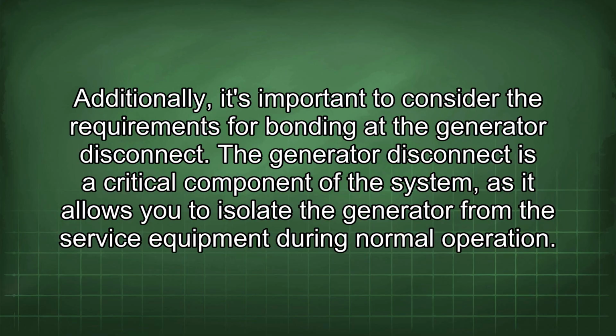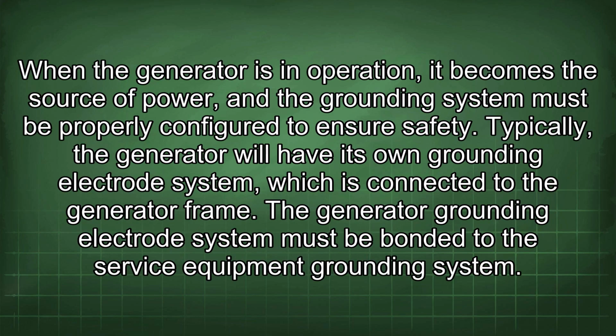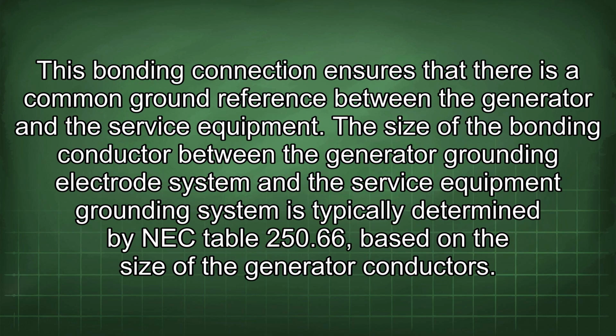The generator disconnect is a critical component of the system, as it allows you to isolate the generator from the service equipment during normal operation. When the generator is in operation, it becomes the source of power, and the grounding system must be properly configured to ensure safety. Typically, the generator will have its own grounding electrode system, which is connected to the generator frame. The generator grounding electrode system must be bonded to the service equipment grounding system. This bonding connection ensures that there is a common ground reference between the generator and the service equipment.